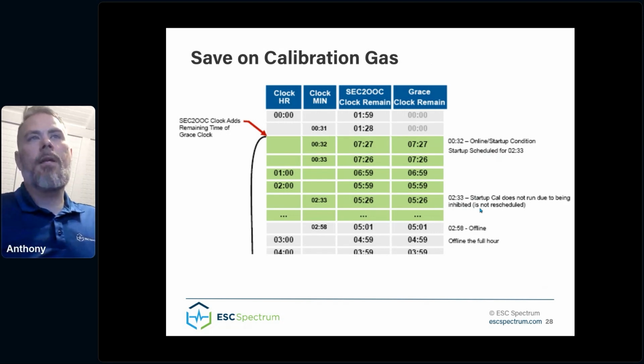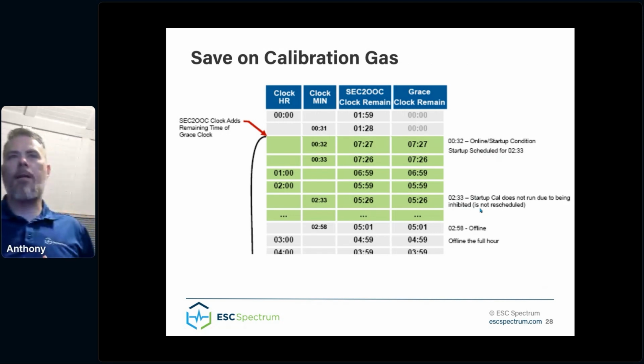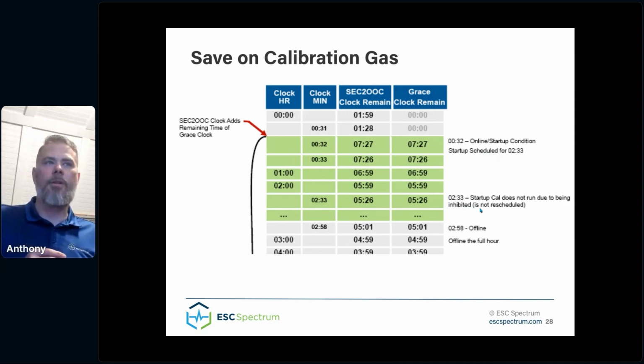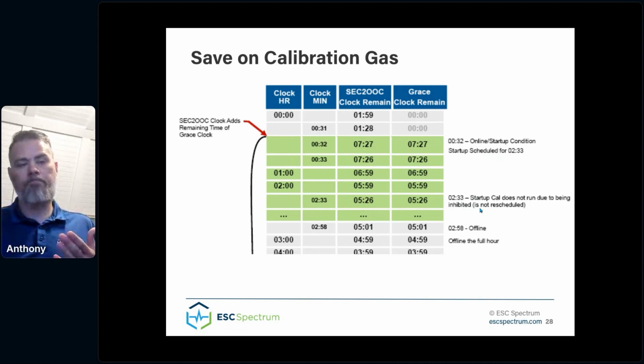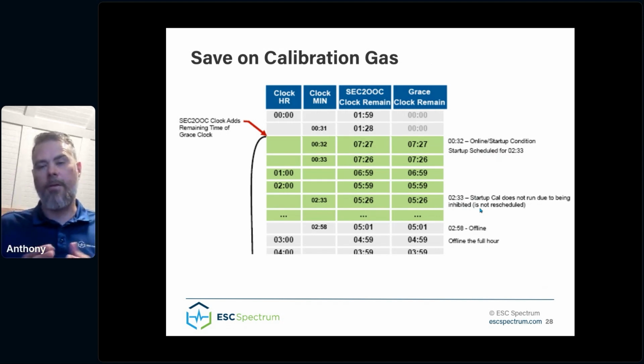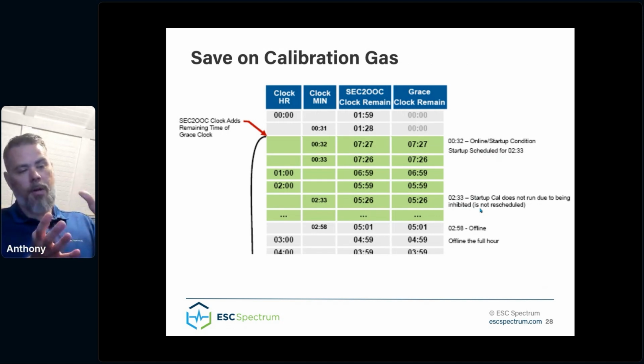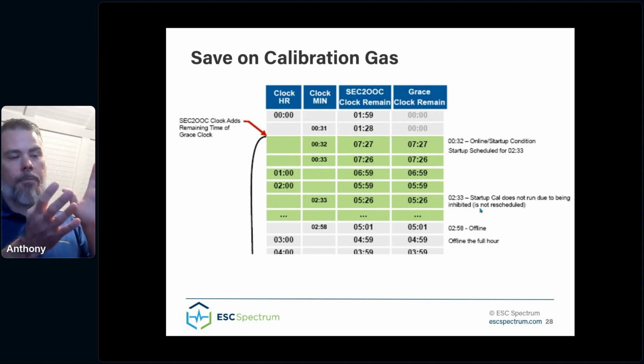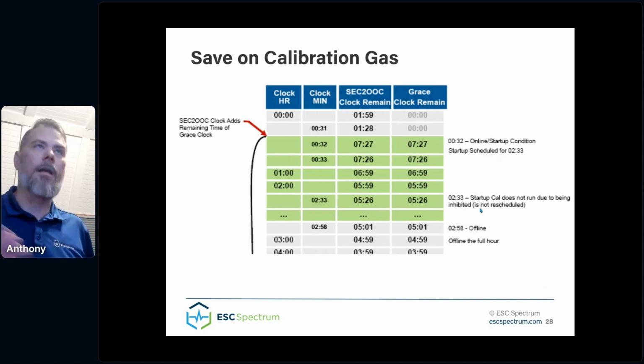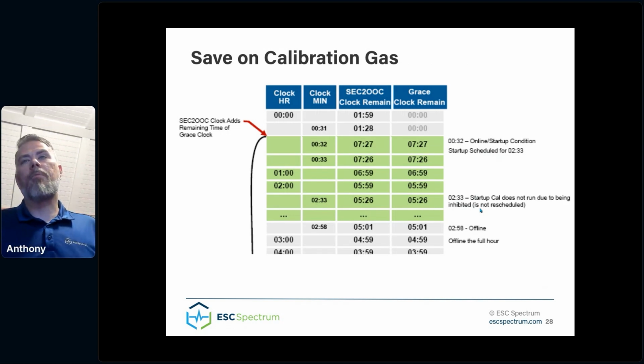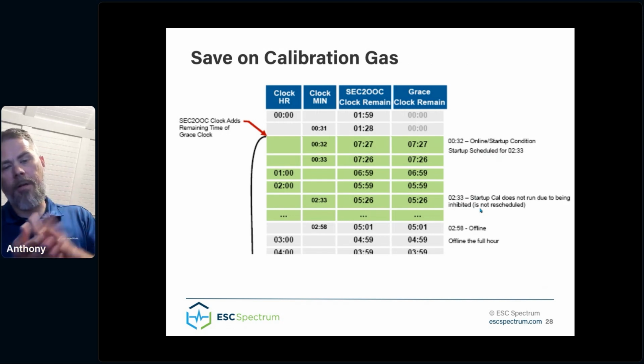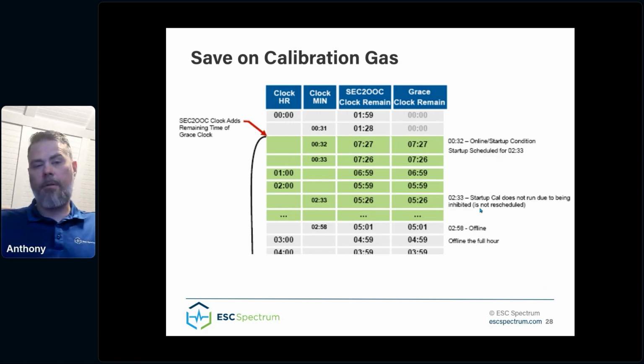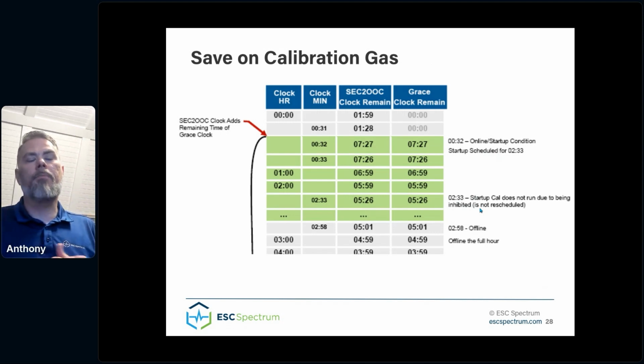But the idea here would be that you would use this in conjunction with the daily calibration that ran online earlier in the day to set an inhibit pattern that you would reset at midnight each day. So the thought is if you've got a unit that starts up and shuts down a lot during the day, or you have a unit that consistently is running at 5 a.m. or whatever it is, daily calibration runs, but then it shuts down, but you know you're going to turn on again in the afternoon. This would give you the ability to prevent that startup calibration from running later in the day when you've already completed a successful online calibration earlier in the day. So it gives you a way that you can save on some calibration gas by preventing those additional startup calibrations from running. That's the real motivation and idea behind this one.